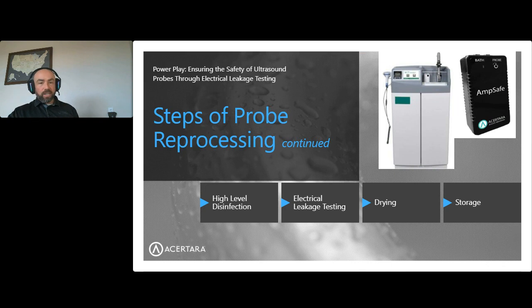I apologize that this slide's got this out of order. I would put electric leakage testing prior to the high-level disinfection. That is because typically that high-level disinfection, specifically for TEE probes, but also for GI probes, is that the probes are going to be soaked in a caustic material. The disinfecting solutions, as you're all aware, are kind of nasty things. So I apologize that this is out of order. I missed that when I was reviewing the presentation. But I would do electric leakage testing first. Make sure that that probe will pass electric leakage testing.